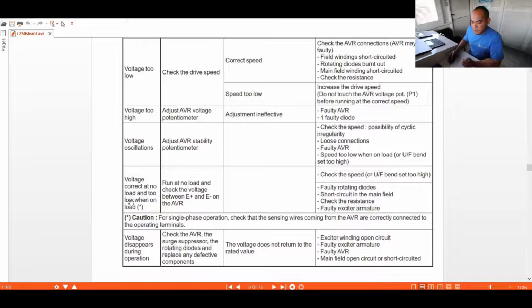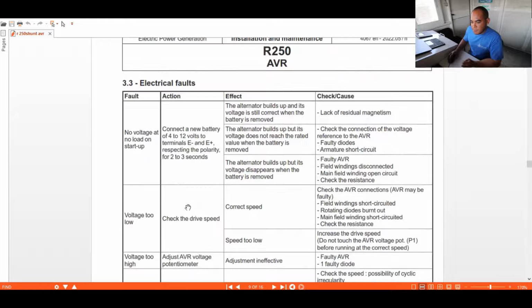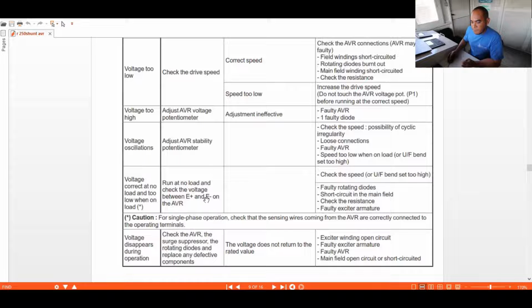Voltage correct at no load and too low when it is loaded. So run at no load, check the voltage between E plus and E minus on the AVR. This is for when you have the correct voltage at no load, but when it has the load, the voltage drops. So you have to check this E and E positive if there is some voltage output to excite your exciter field. Okay. So this is how you do the fault finding.